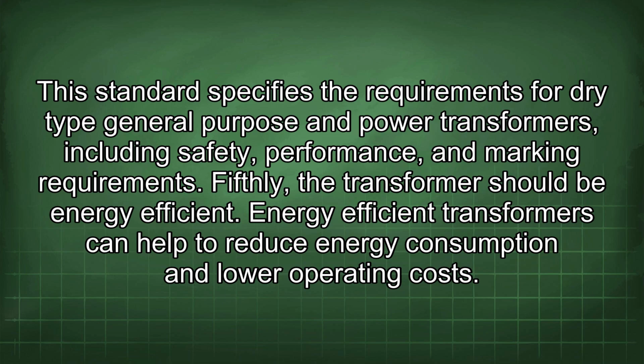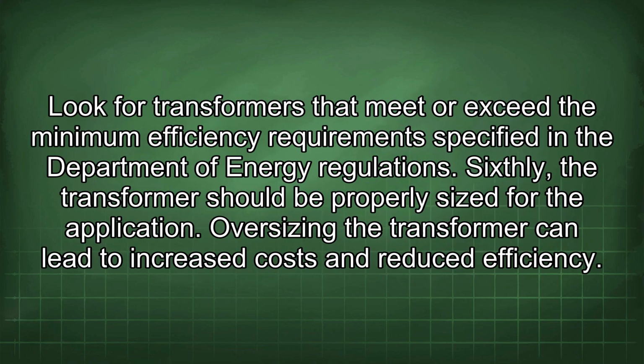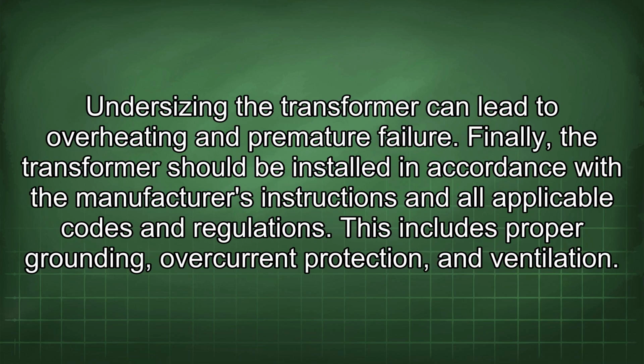Fifthly, the transformer should be energy efficient. Energy-efficient transformers can help to reduce energy consumption and lower operating costs. Look for transformers that meet or exceed the minimum efficiency requirements specified in the Department of Energy regulations. Sixthly, the transformer should be properly sized for the application. Oversizing the transformer can lead to increased costs and reduced efficiency. Undersizing the transformer can lead to overheating and premature failure.